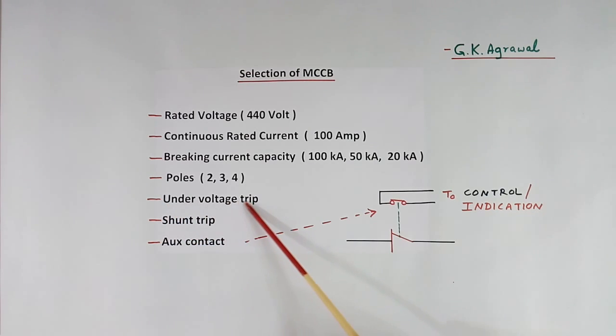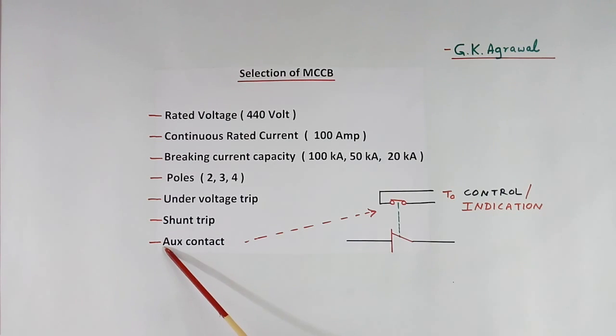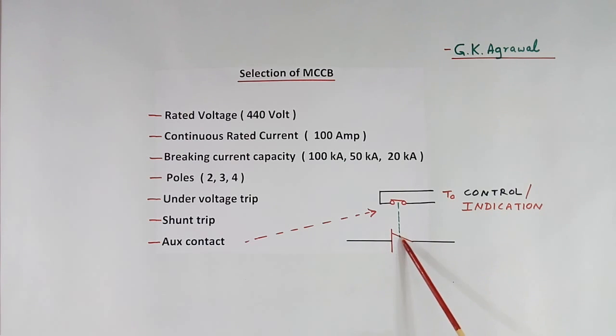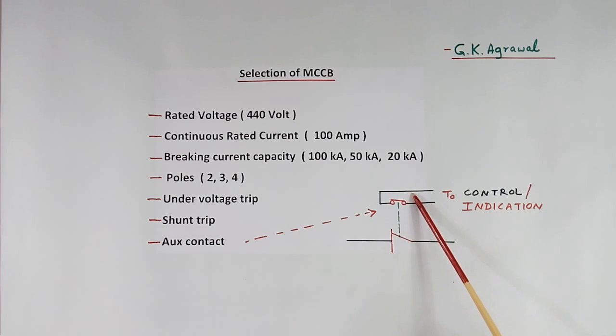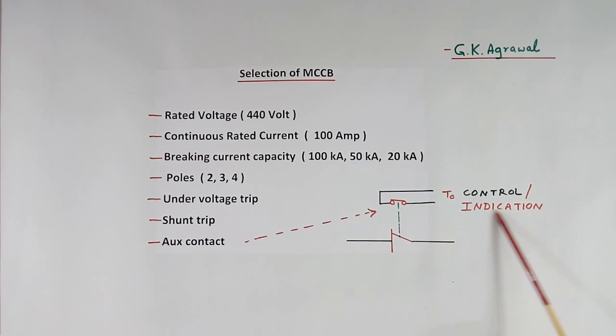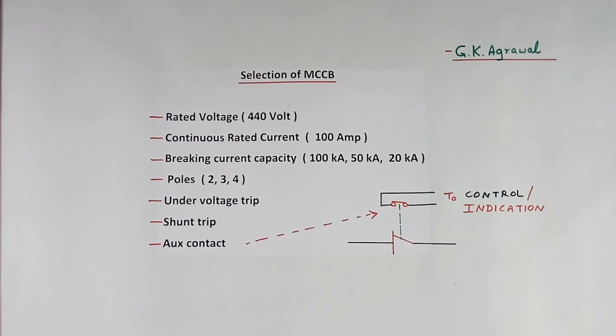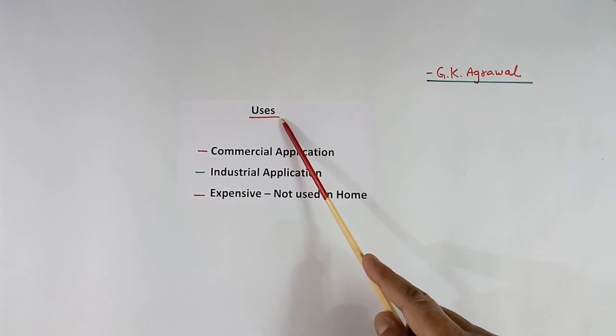Then we should know the under voltage trip requirement, whether we want a shunt trip coil or not, and also the auxiliary contact requirement. The MCCB trip contact is mechanically connected to another contact. When this trips, the auxiliary contact also becomes open. This is used for control, indication, or alarm purpose — so when this MCCB trips, some alarm will be generated.